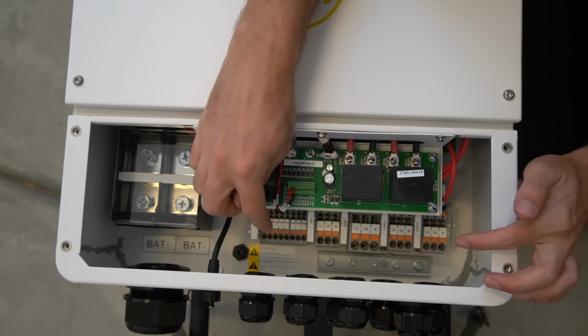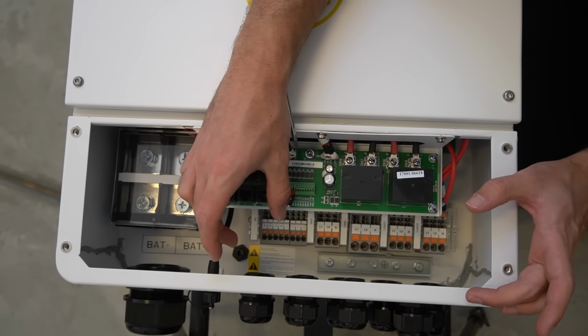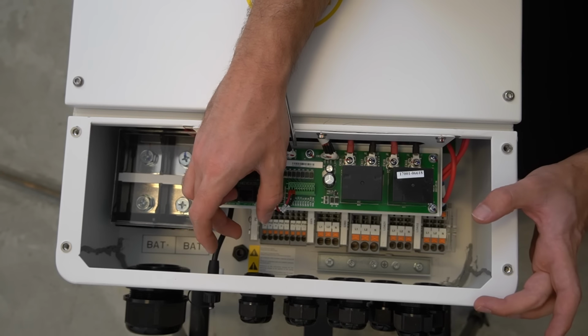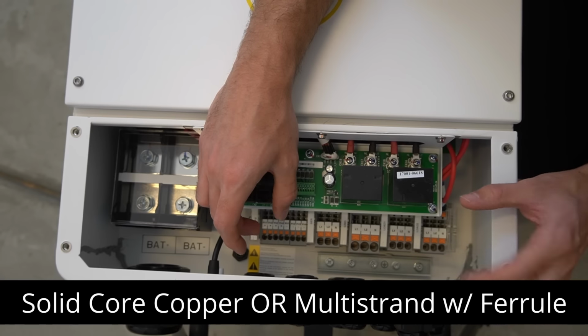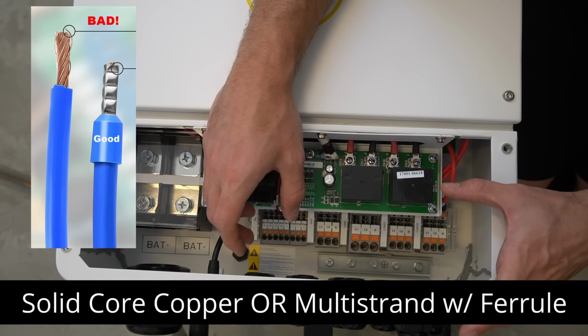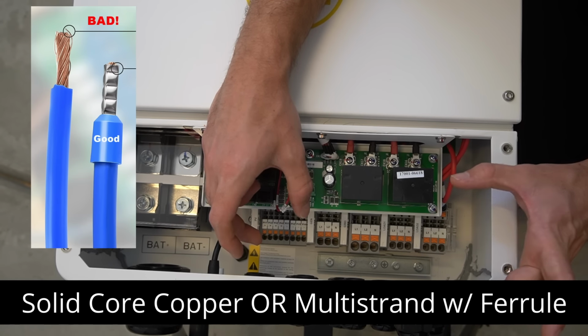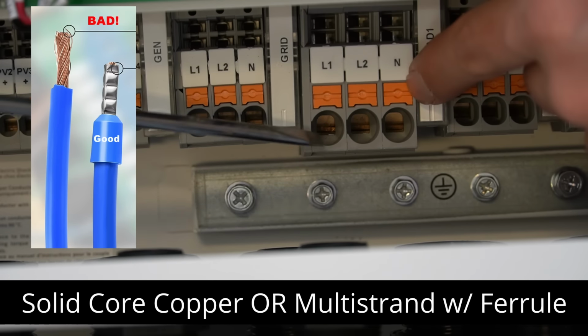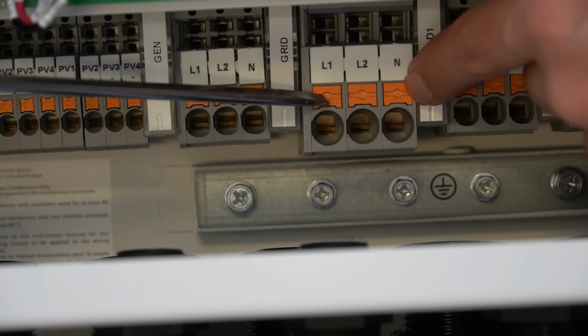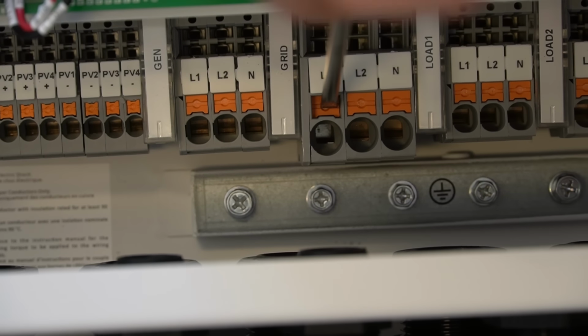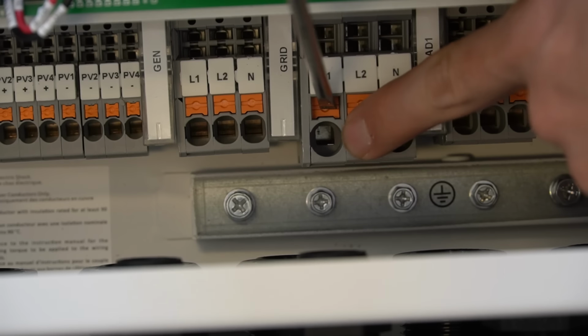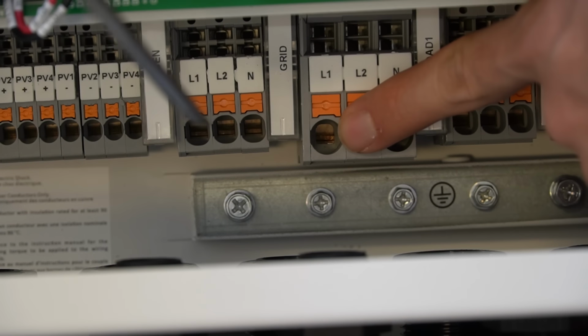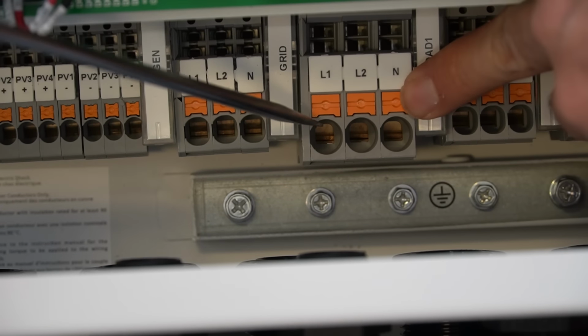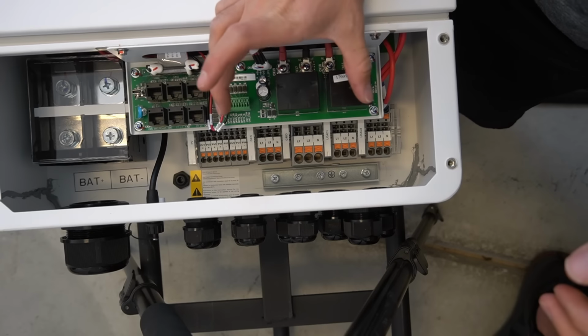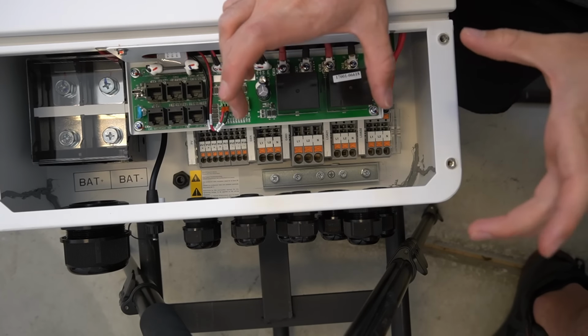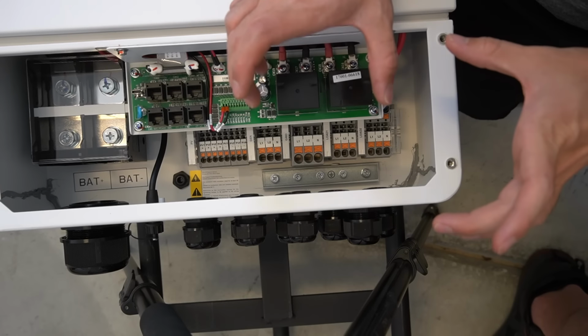Now we really need to talk about these terminals because they're very different and we've never seen them on the channel previously. These have to be used with solid core wire or a multi-strand wire inside of a ferrule. Now when you want to install the wire, you need to use a flathead screwdriver on this orange square, push it down pretty hard, and then insert your wire or ferrule and then release it, and then gently tug on it to make sure it's actually holding. These are very easy to use, but you cannot use multi-strand wire. Do not even try that.